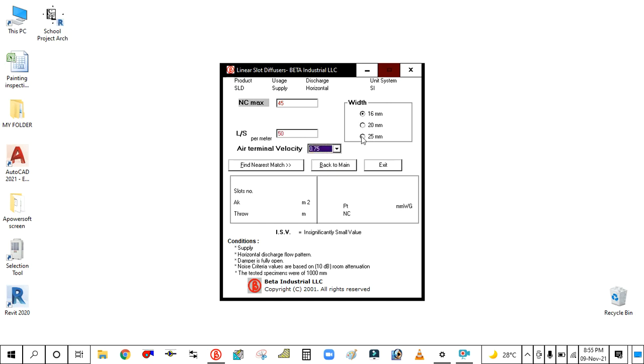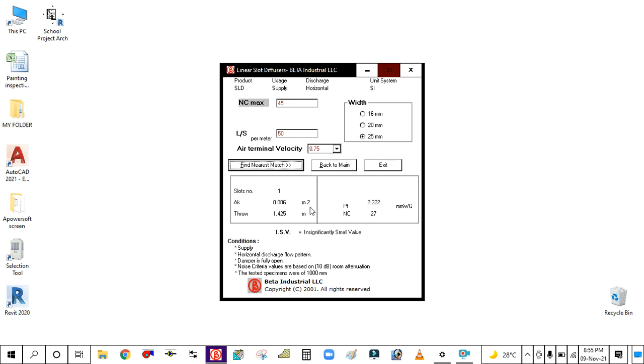Then simply click here find the nearest match. You are getting a number of slots is one, critical area is 0.006 square meter, and throw is 1.4 meter. Total pressure drop is 2.32 mm of water gauge, noise criteria is 27.